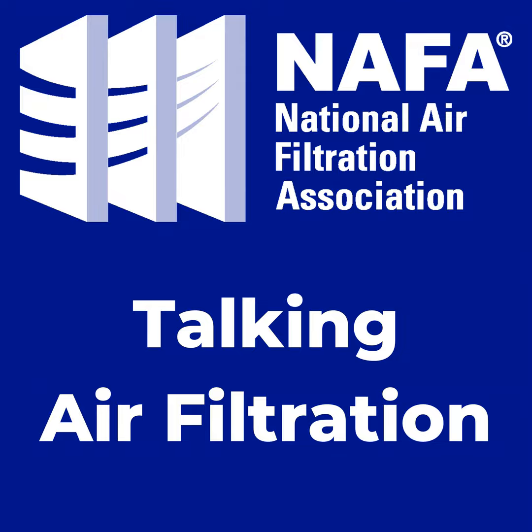And the benefit to that is when you look at different particle sizes above that MPPS, the PTFE will always outperform it, because as that efficiency rises, you've already met your lower minimum point sooner. So that's the benefit of using these PTFE medias in HEPA filter applications.